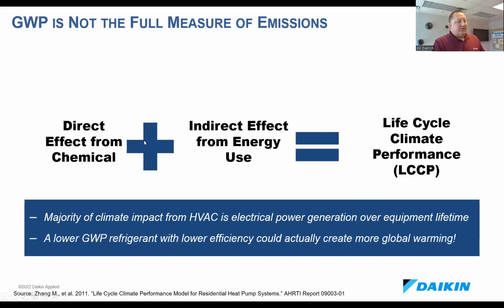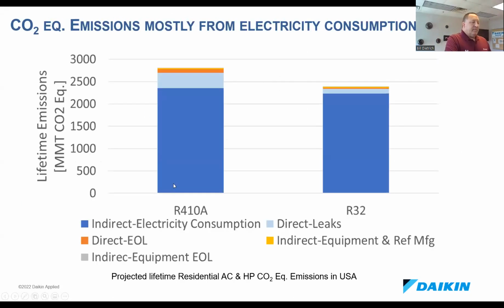Now this mix will change, and as we drive towards more renewables, the direct effect will become more important. But if we looked at a study for a residential AC with R410A and one with R32, in both cases the indirect effect of electricity consumption was by far the biggest contributor—the direct effect, essentially leaks, is the light blue stuff here and here, and then there's end of life type things. This is big, but as we drive to renewables, theoretically at some point we could get the indirect effect to go away, and if you're on a low GWP direct effect, we'd have a significant impact for the climate.